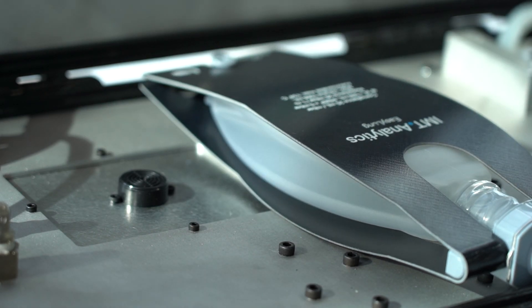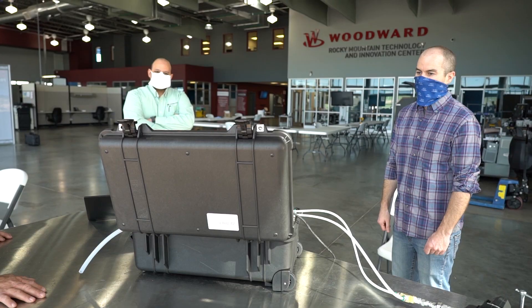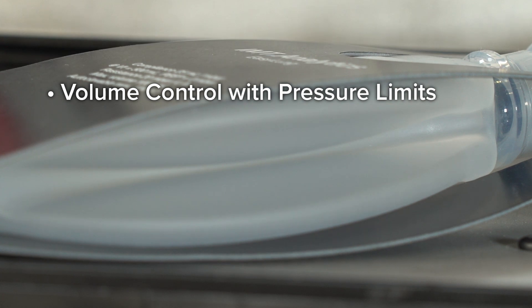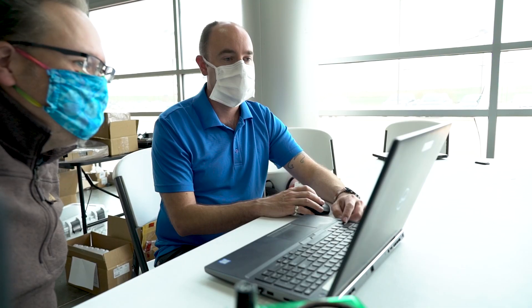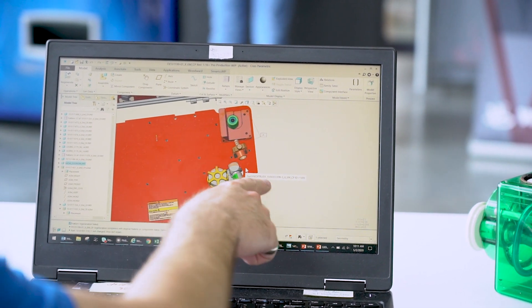After consulting with pulmonologists, respiratory therapists, medical school professors, bioengineering professors, and respiratory technicians, the current operating modes we decided on were volume control with pressure limits, pressure control with volume limits, and pressure support. We needed to be able to control breathing for a patient when they are incapacitated, and yet be able to assist them to breathe when they are recovering and able to take a patient-triggered breath.